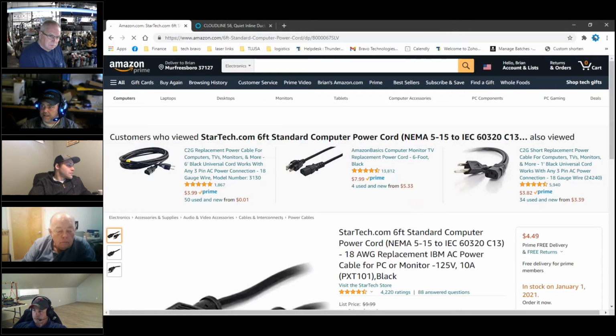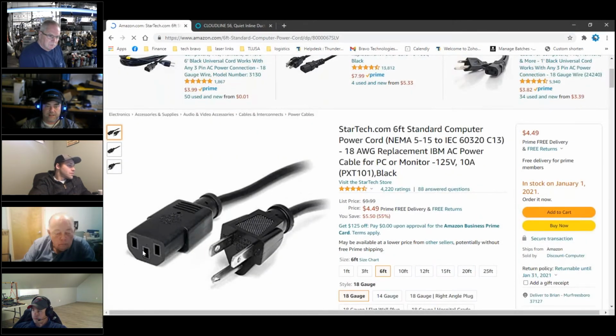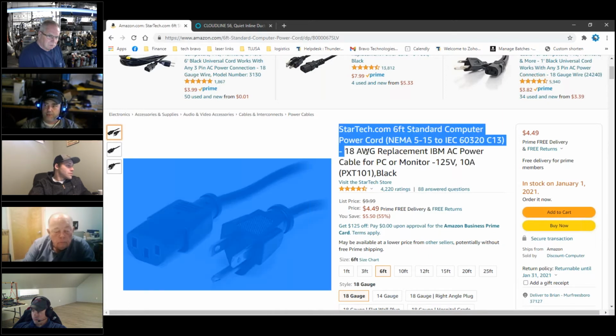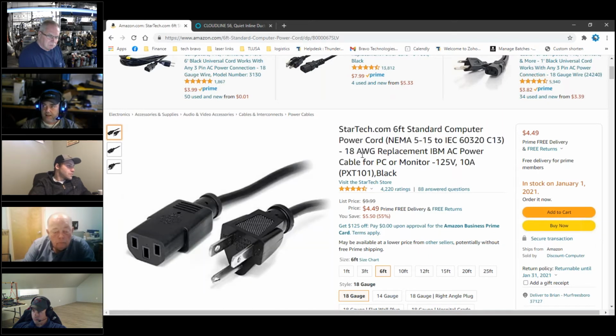The fan takes a standard IEC connector, the same one you see on the back of your computer monitor or desktop PC. You need to pay attention and make sure it's at least 18 AWG, though I'd prefer 16 AWG honestly. I think 18 will be all right, and that's probably what's in there.